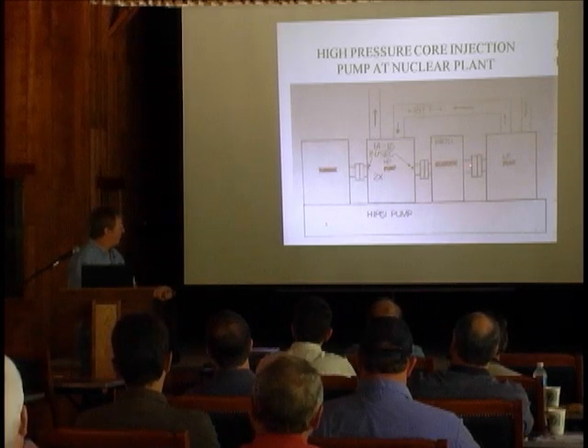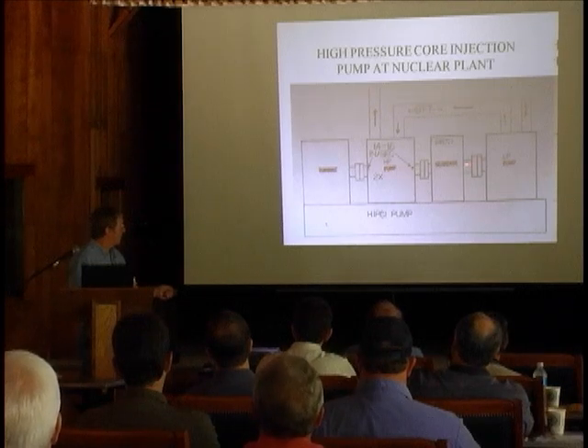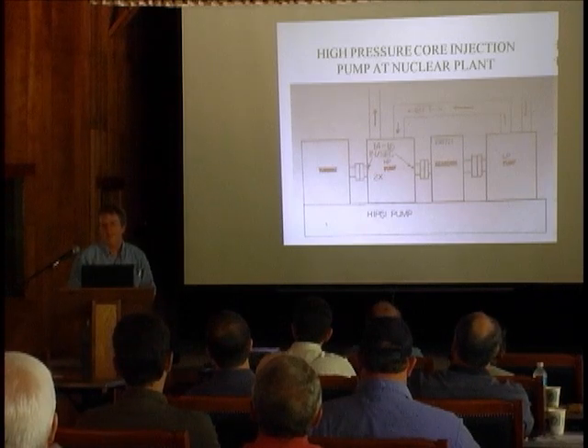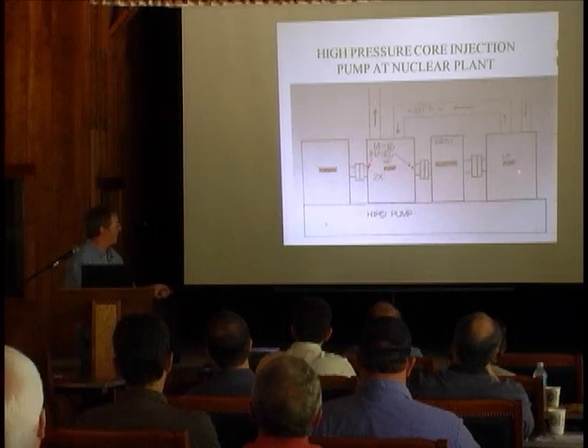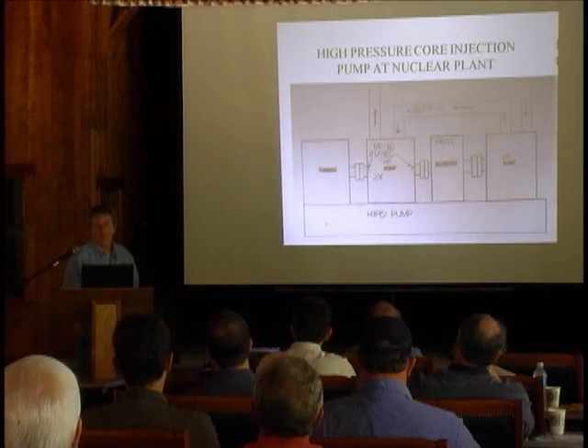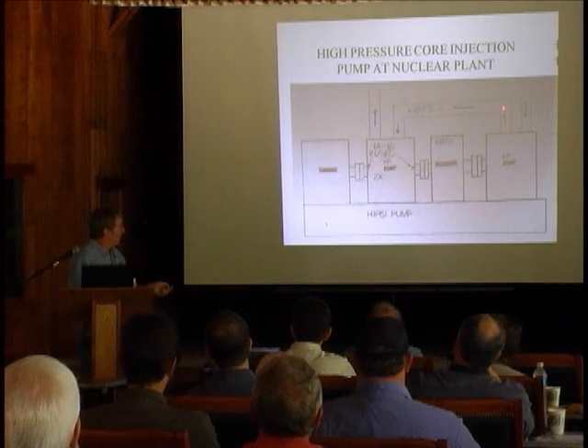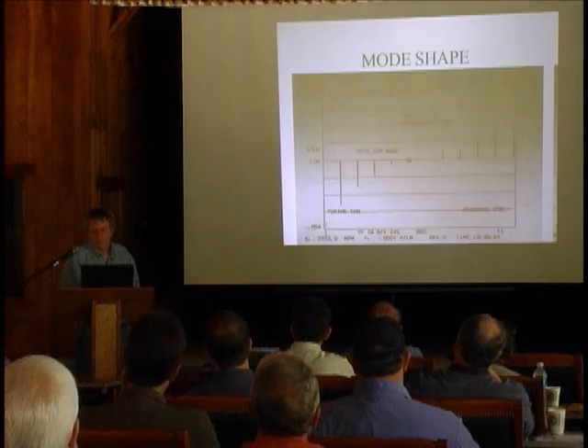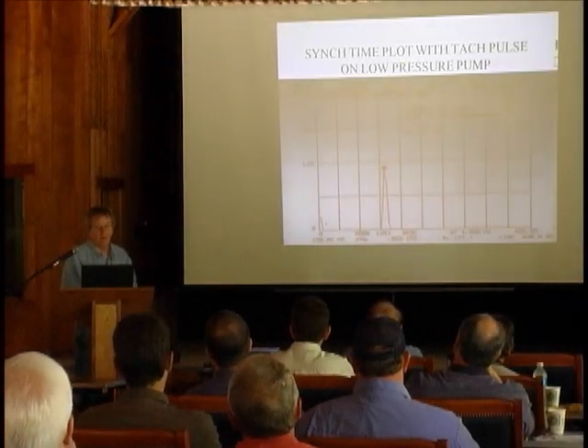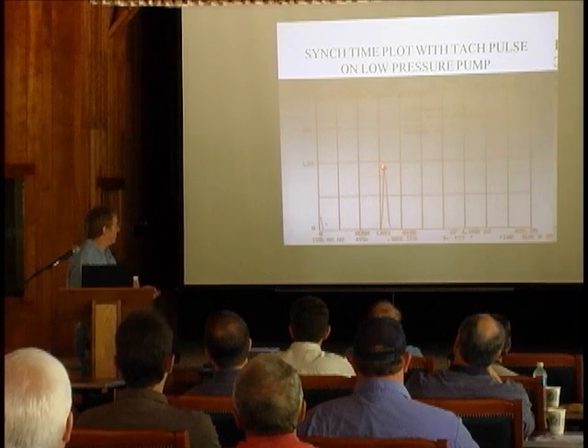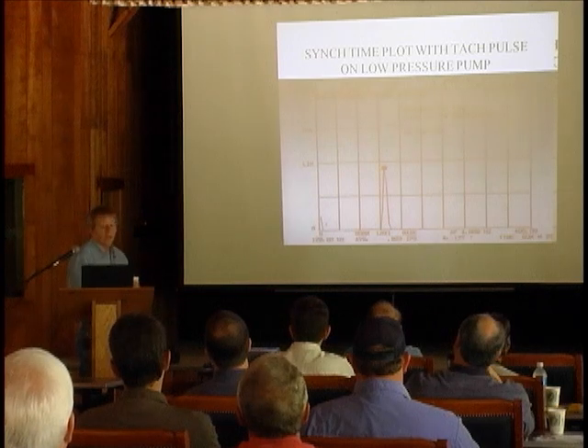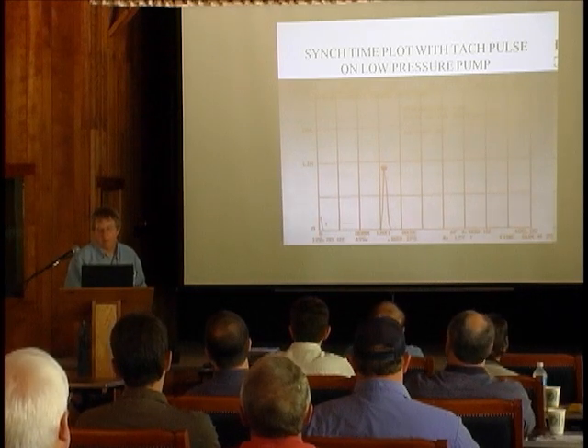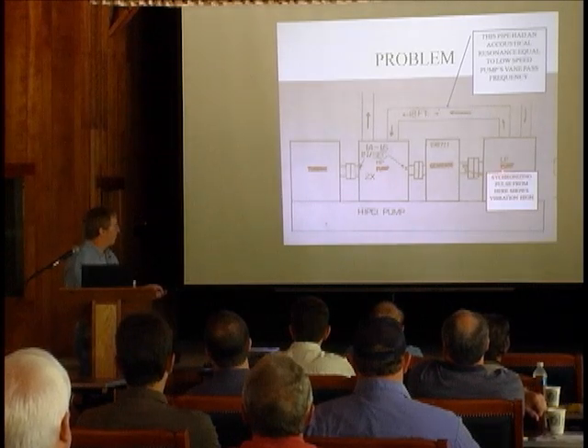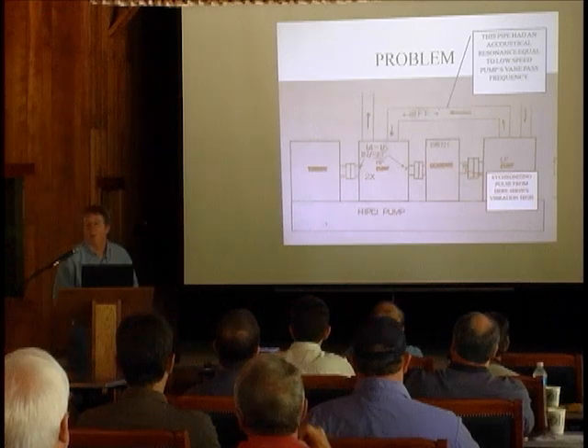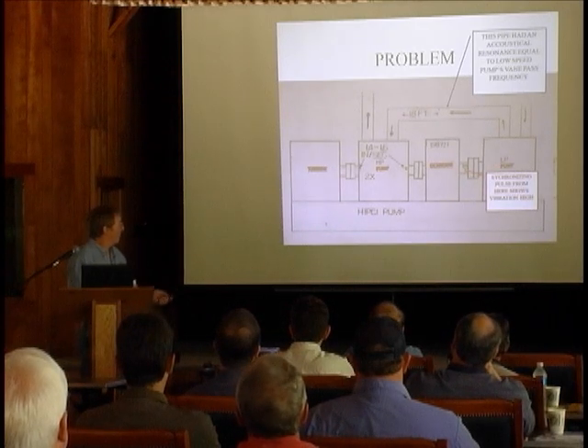So I put a piece of shiny tape down here on this gearbox, measured the vibration on this gearbox, did synchronous time average, it goes bloop, bloop, bloop, and it stays there. That means the vibration on this pump is phase locked to this pump, has nothing to do with this pump. So I did synchronous time averaging on it, and bingo, 25 averages, it just locks in and it stays there. That means the vibration on the high pressure pump is from the low pressure pump. It has nothing to do with the high pressure pump. The low pressure pump is just doing fine, by the way.